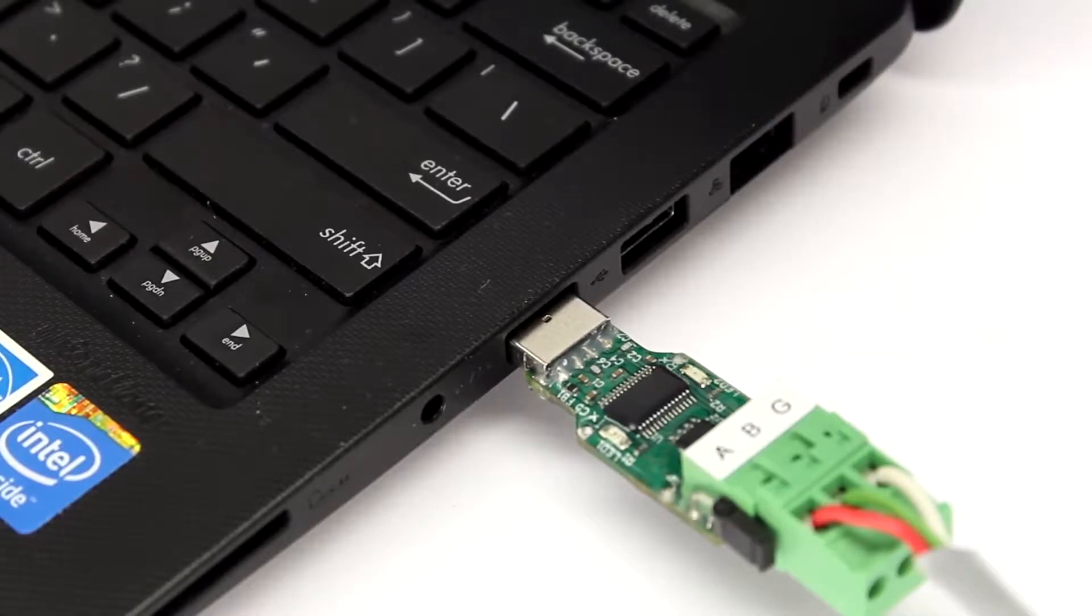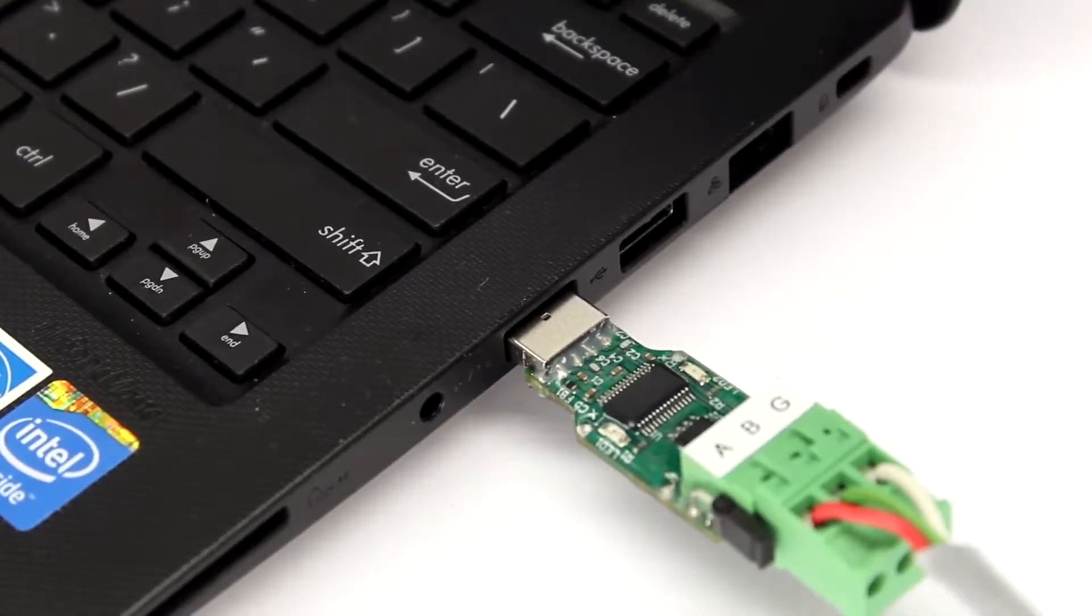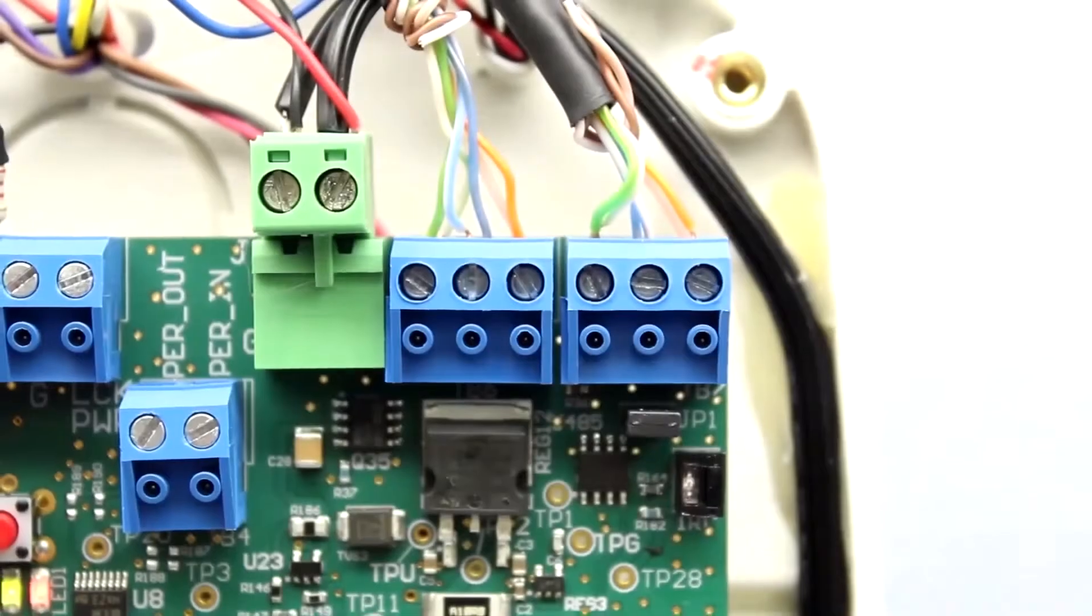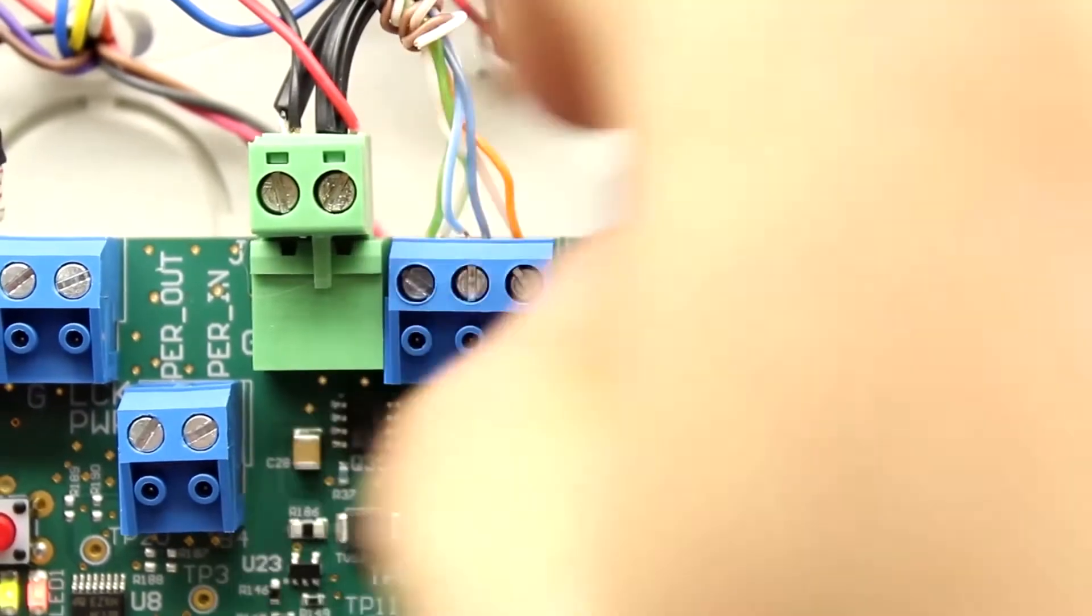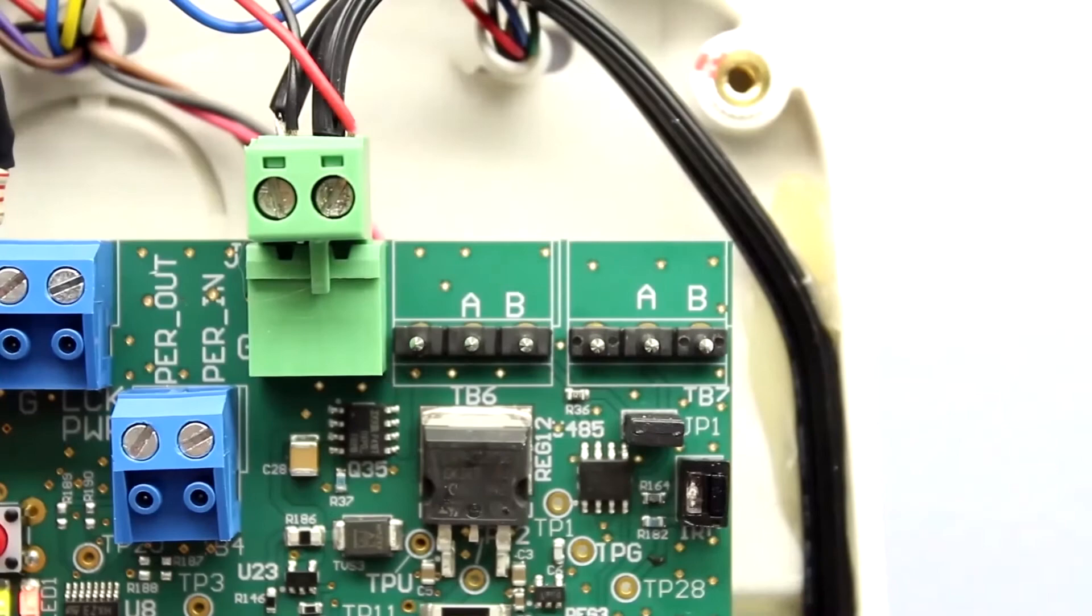Windows should automatically find and install the drivers for the CA 702 and assign a COM port to it. Starting at the first door controller to be programmed, remove the TechCare 700 network connections from TB6 and TB7. Connect the programming cable to either location.